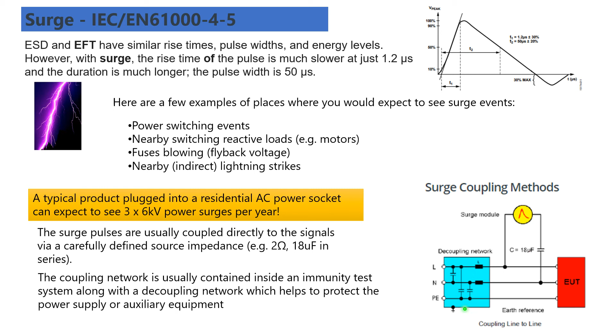So what are the failure modes? Surge basically involves a lot of energy. The current involved can easily exceed 100 ampere for a short period of time. With this amount of energy, it is very easy to damage your product. During my testing, whenever I used it on my devices, I have seen complete frying of the ICs. Sometimes cable breakdowns. We have seen thermal issues going to different temperatures, and arcing is very common. And if you have motor-type devices, we have seen damage of the motor winding.